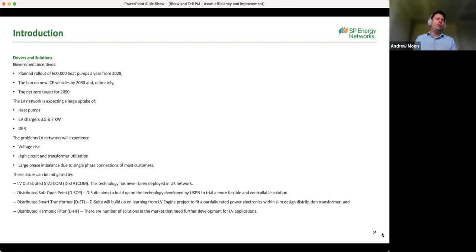We also see on interconnected networks that load can share unevenly between secondary substations, which can lead to low impedance paths taking the load, with those transformers being near their limits while other transformers are underutilized. And as we put heat pumps and big loads onto the network that are continually operating, not variable but operating throughout the day, we could see large phase imbalances, which will increase the utilization of one phase and leave the other LV phases fairly unutilized.